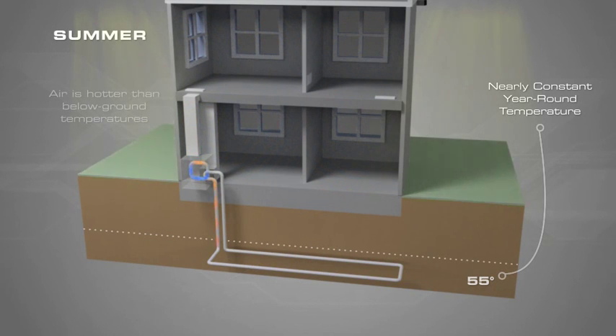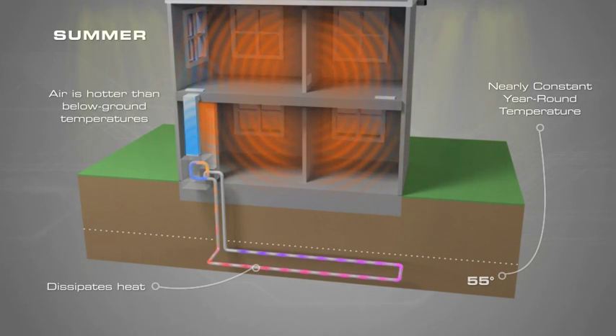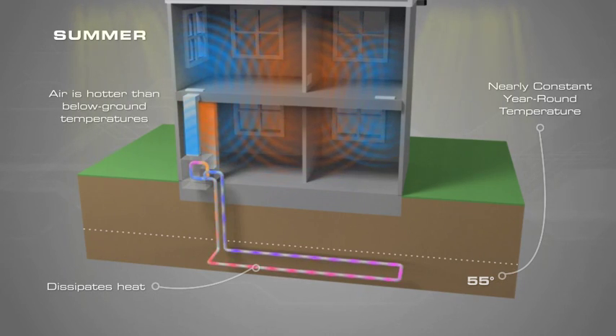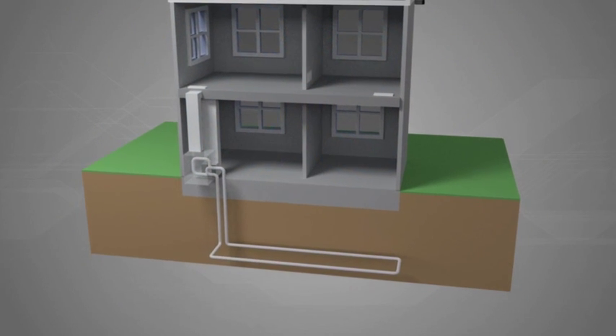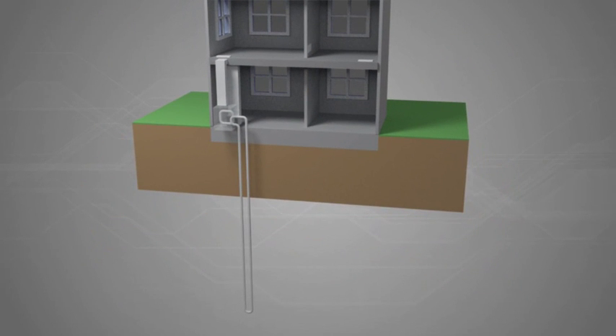In the summertime, the system works in reverse. When it's hot outside, the temperature below the surface is cooler than the summer heat. So the fluid in the loop absorbs heat in the building and sends it underground. The ground's lower temperature cools it, and it's circulated back into the building. If you don't have a lot of space, you can go straight down and use a vertical loop system instead of the horizontal loop system.